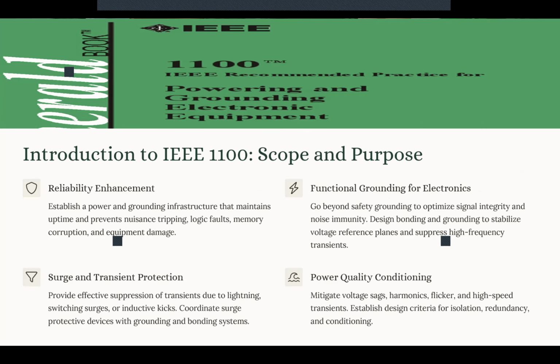Now, IEEE 1100, as we mentioned, is a recommended practice, not a mandatory standard. It provides the guidelines for powering and grounding sensitive electronic equipment. This standard basically aims to prevent failure, data corruption, or operational disruption in environments where even a minor electrical disturbance can cause significant damage or even downtime.